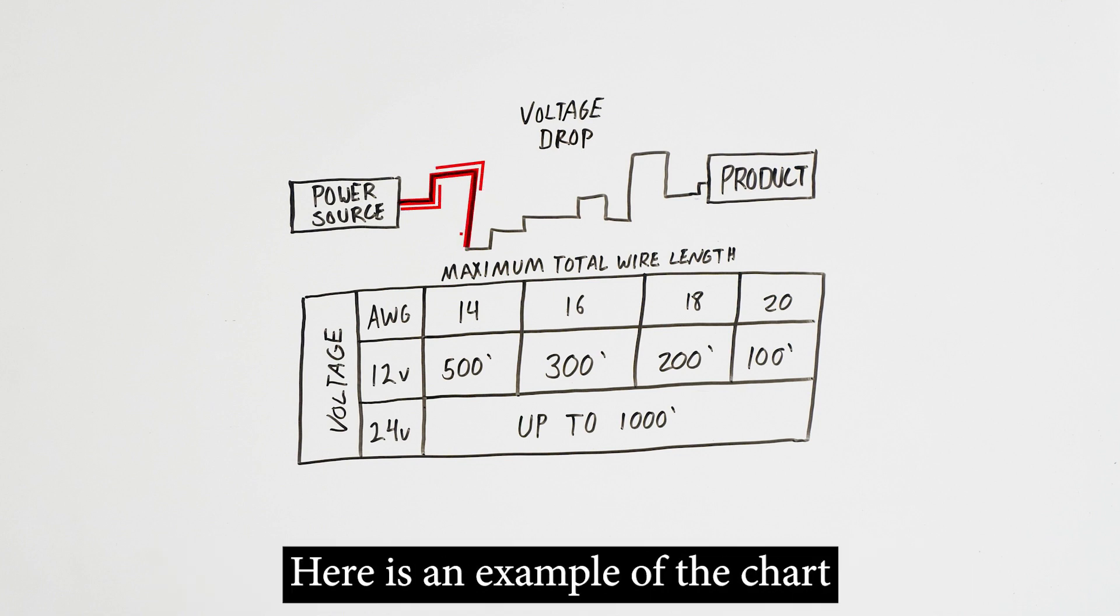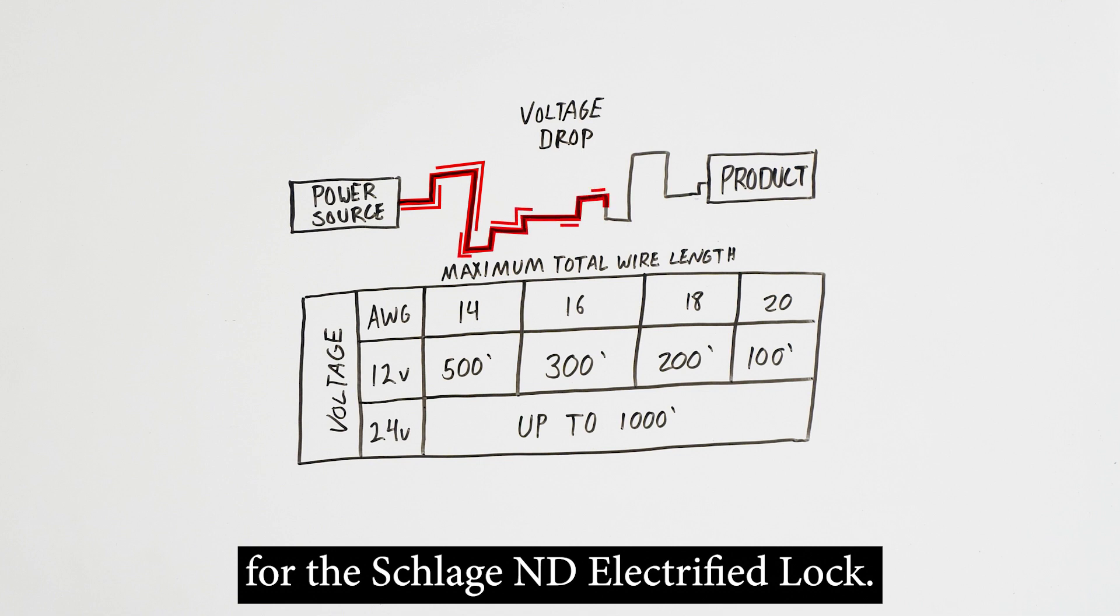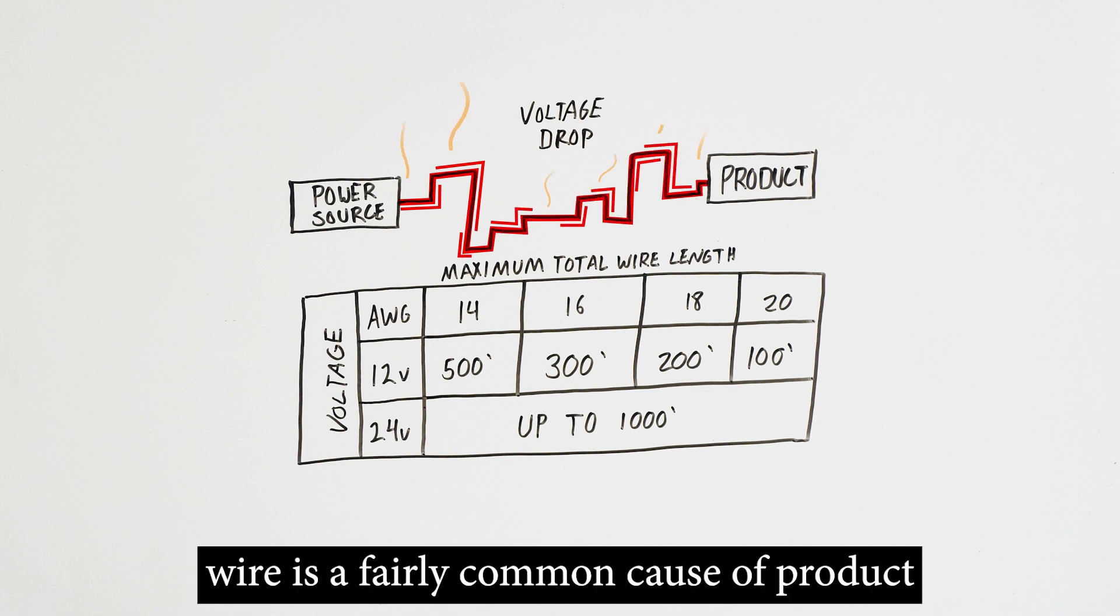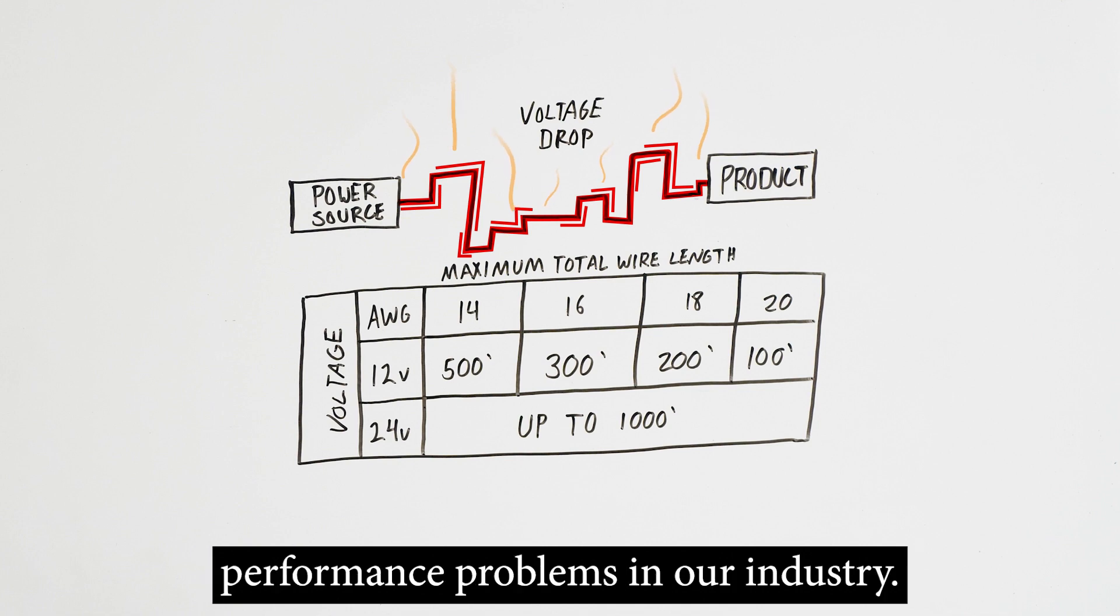Here is an example of the chart for the Schlage ND electrified lock. By the way, the use of the wrong gauge of wire is a fairly common cause of product performance problems in our industry.